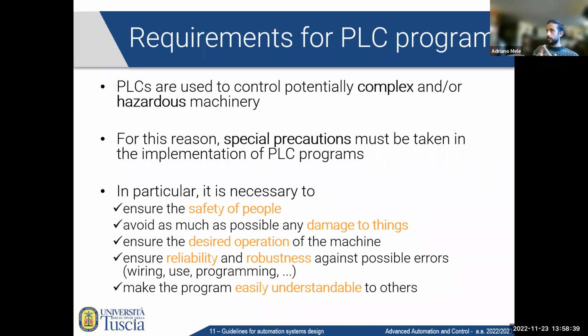That's, for example, the reason why when you have a PLC, all the outputs are insulated from the field. In that case, you might burn one contact, maybe break one photodiode in the contact, but you're not breaking the electronics behind it. So you just change the wire, change the address, and continue operating without having to dismount the PLC, mount it again, load the program, test everything, do the wiring from scratch, and so on.